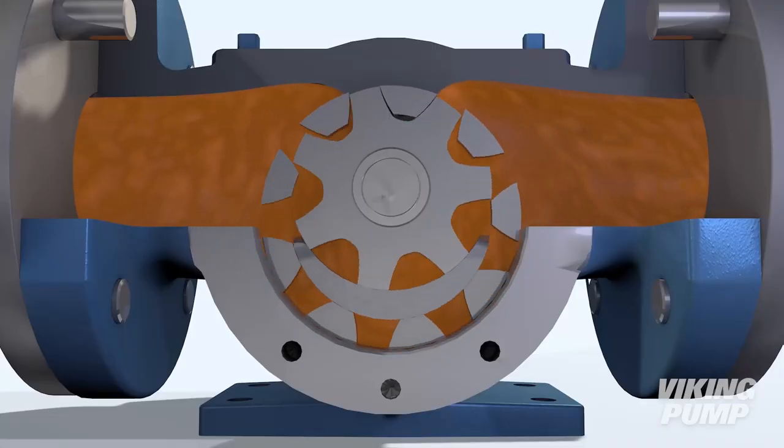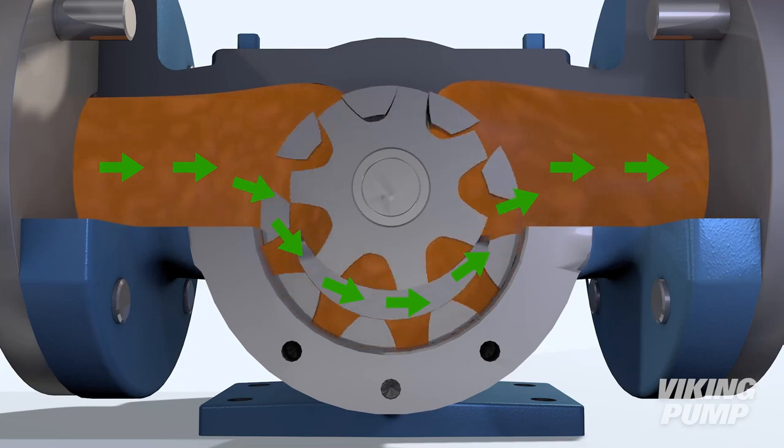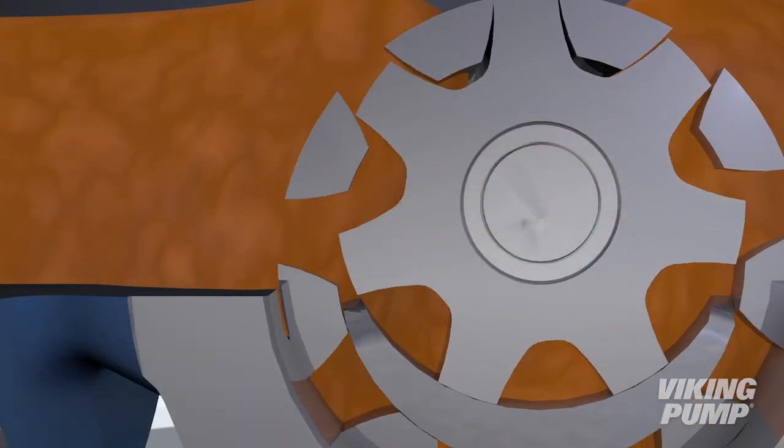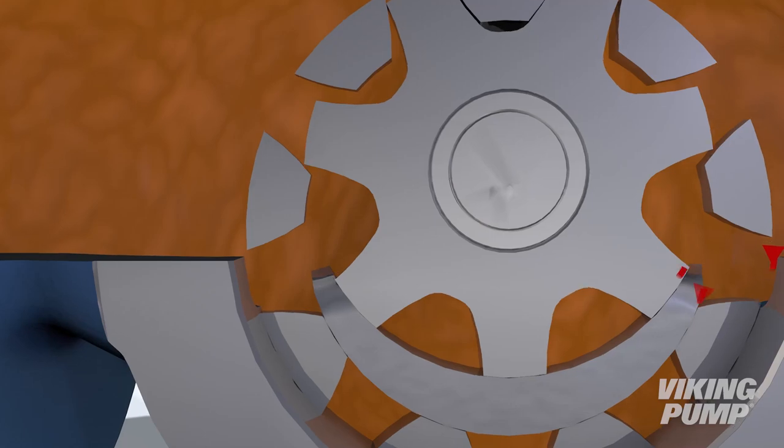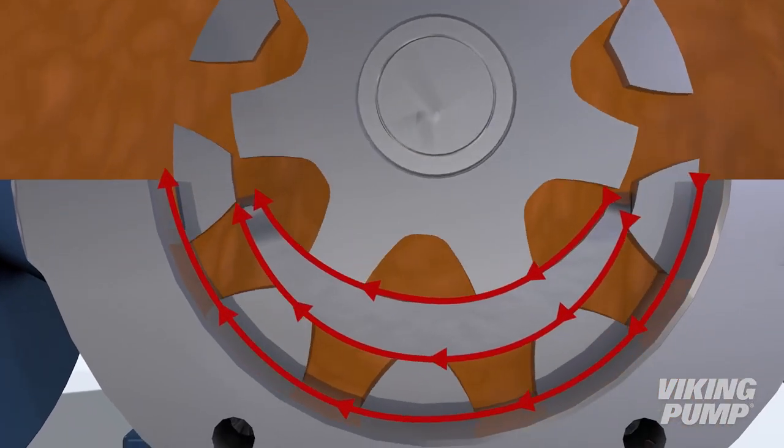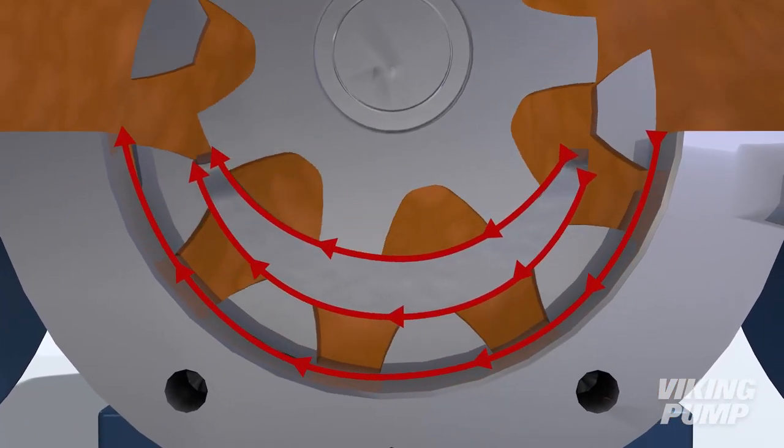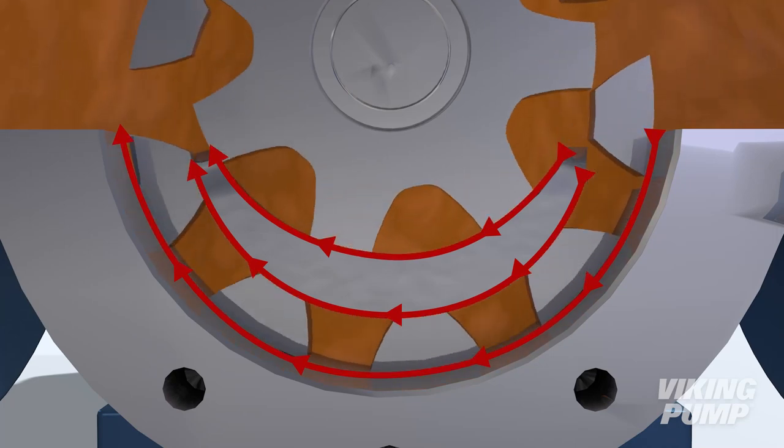In a rotary positive displacement pump, the flow direction follows the rotation of the gears or other pumping elements. Small clearances between and around the gears allow them to rotate freely, but this also allows for a small amount of liquid to leak or slip back from the high pressure side to the low pressure side of the pump.